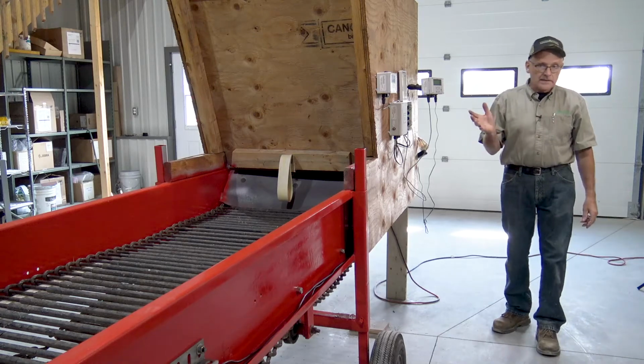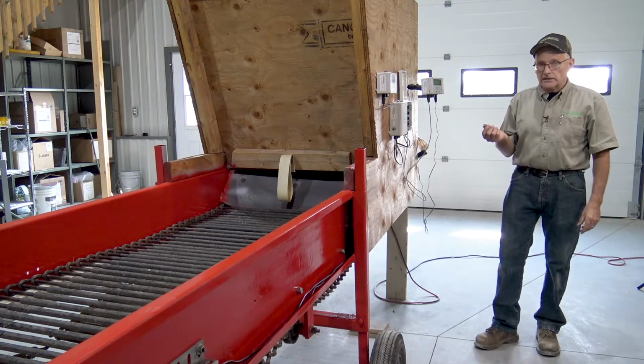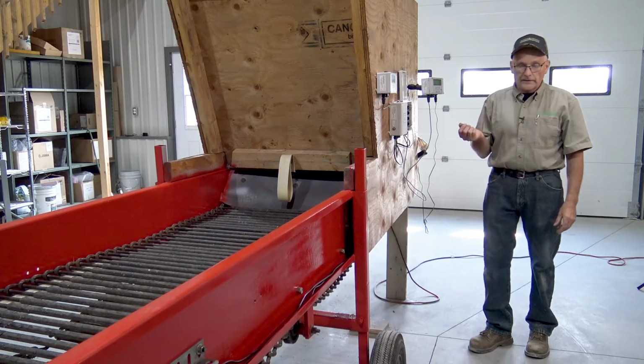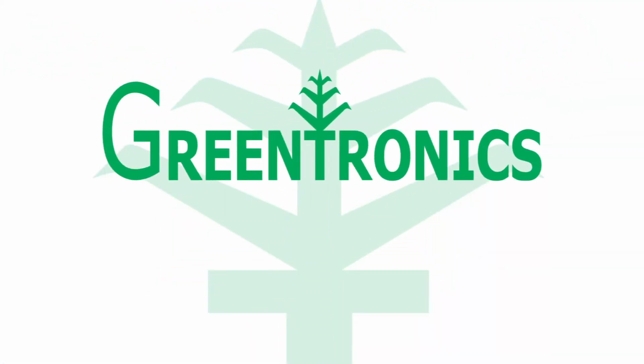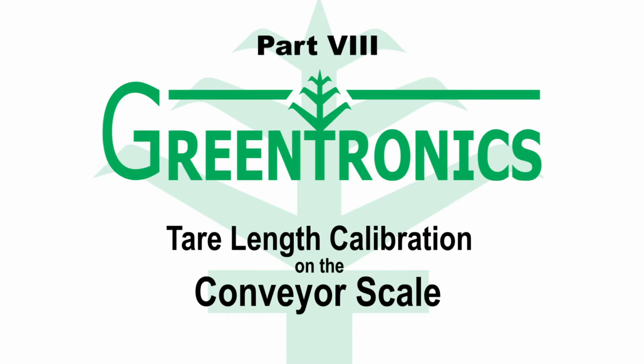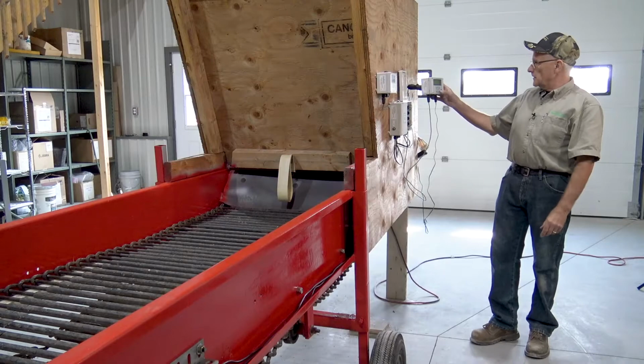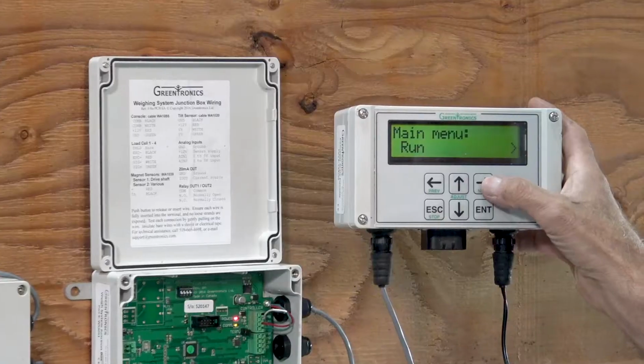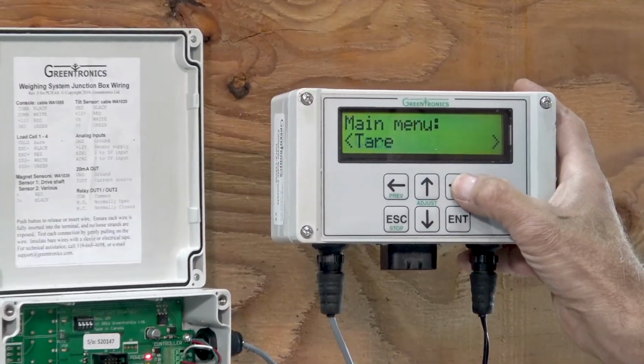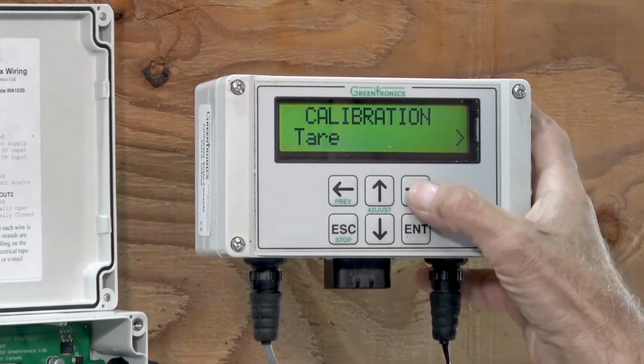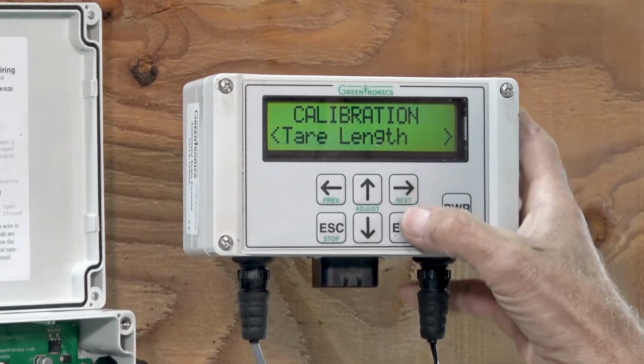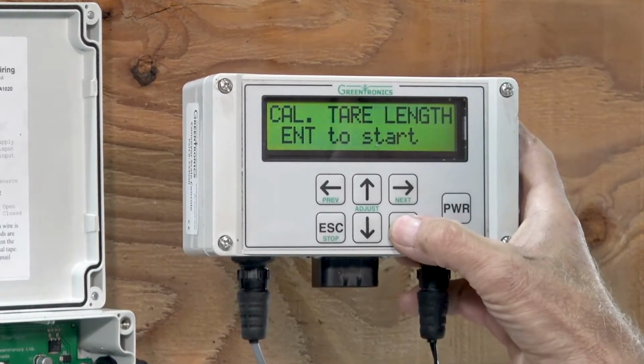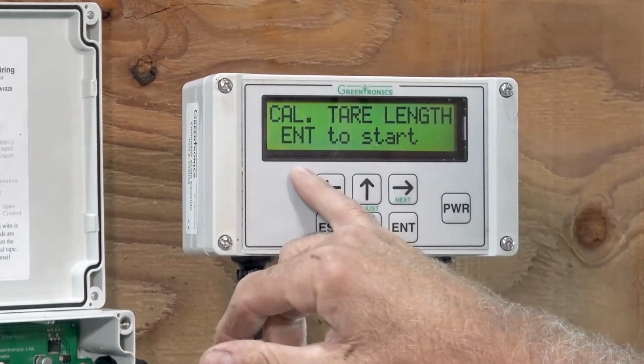So our next step with setting up the conveyor scale is to do a tare length calibration. And that is found on the console here. We're going to the right to our calibrate menu. We hit enter and we go to tare length. And now all I have to do is enter to start.